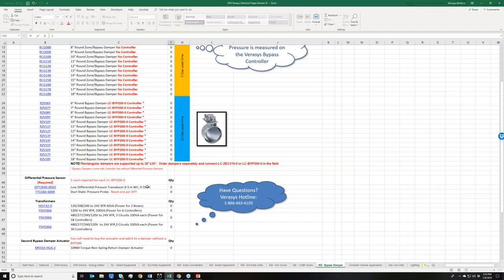What doesn't come with the bypass controllers is the duct static pressure transducer and the probe. The reason being is that you don't necessarily have to use these sensors. All you have to use is a pressure transducer and probe that fits the 0 to 5 inches of water column and a 0 to 5 VDC signal. The Verasys bypass controller is set up to receive only these inputs. If you go outside of this range, your bypass is not going to open properly.